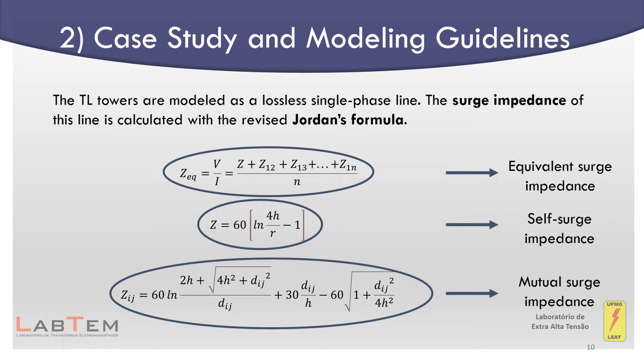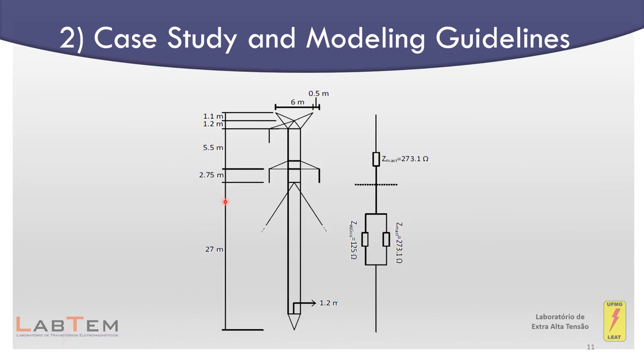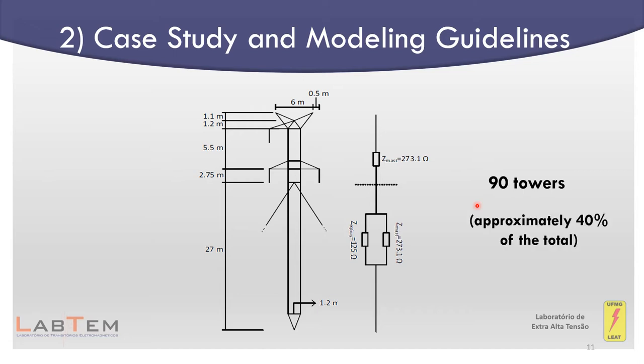On the left is represented the guyed tower geometry, with the ATP tower model on the right. Each guy wire was represented as a single vertical conductor whose surge impedance was calculated using the expression shown previously. The equivalent impedance of the four guy wires was determined by dividing that of a single wire by four. The equivalent impedance of the guy wires is placed in parallel with the mast surge impedance at their connection point, as indicated in the tower model. 90 of the 220 towers are guyed structures.